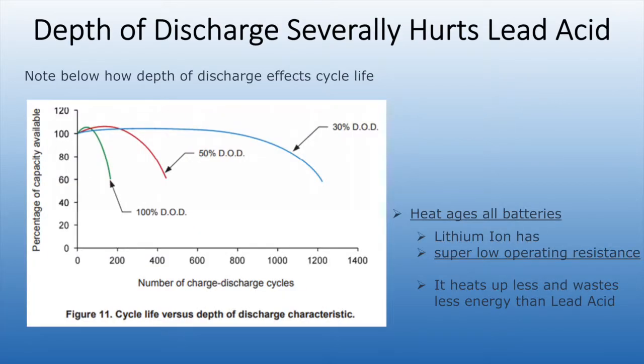This chart further shows how the depth of discharge severely hurts a lead acid battery. If you look at the chart, first of all, on the left-hand side, you have a percentage of the capacity left, and we consider at 80% you have no capacity left. That's when you're supposed to change your batteries. If you go across that 80 percentile mark, and you look over at a 30% discharge, you can see that the lead acid gets about maybe 1,100 discharges. You can see why they only want to do a 30% depth of discharge and why you need a lot more lead acid, and it gets heavy. Look at the 50%, look at the 100%. At 100%, you're only going to get maybe 70, maybe 120 discharge cycles compared to 1,000 or 800 that you would get with lithium ion, a much better ratio.